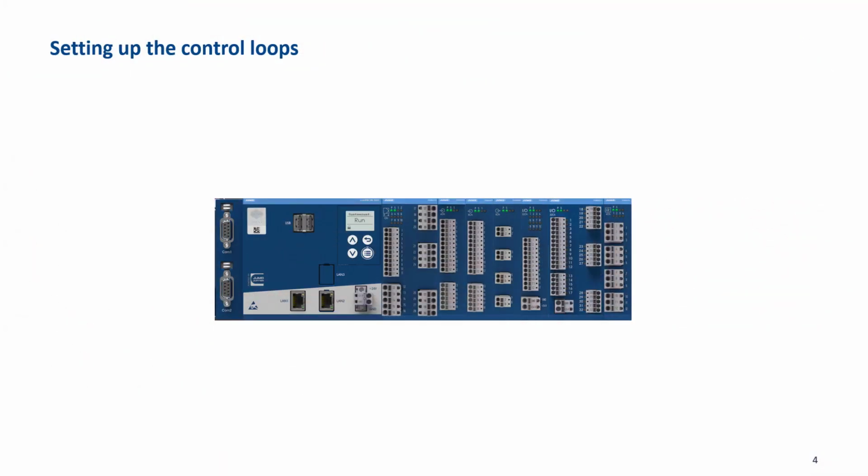First, I configure the settings for the control loops and smartware setup. I measure the temperature with a PT100 and 3-wire circuit. A continuous controller is used, and the actuator is controlled via a 4 to 20 mA signal. The humidity is available as a 4 to 20 mA signal. The controller also operates continuously, and the humidifier is controlled by a 4 to 20 mA signal.